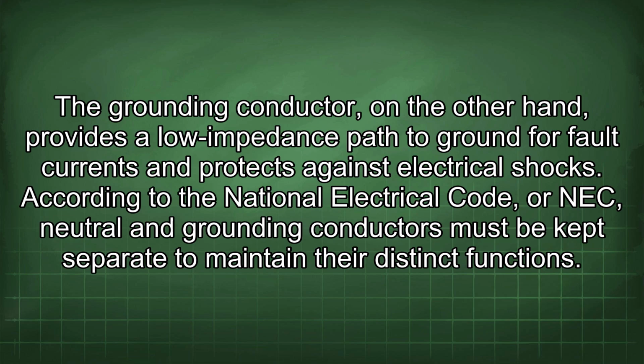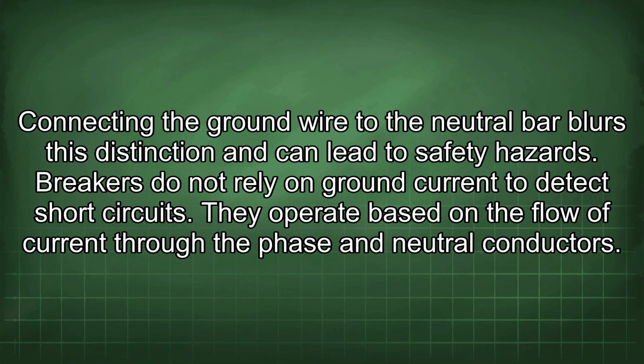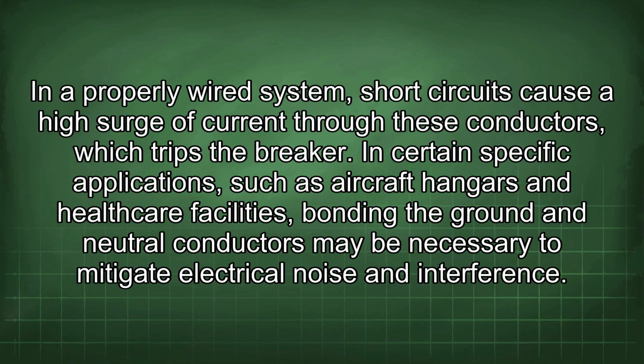According to the National Electrical Code, or NEC, neutral and grounding conductors must be kept separate to maintain their distinct functions. Connecting the ground wire to the neutral bar blurs this distinction and can lead to safety hazards. Breakers do not rely on ground current to detect short circuits. They operate based on the flow of current through the phase and neutral conductors. In a properly wired system, short circuits cause a high surge of current through these conductors, which trips the breaker.